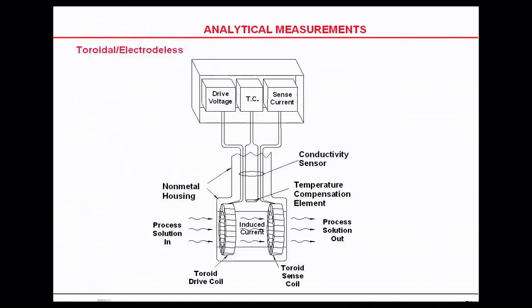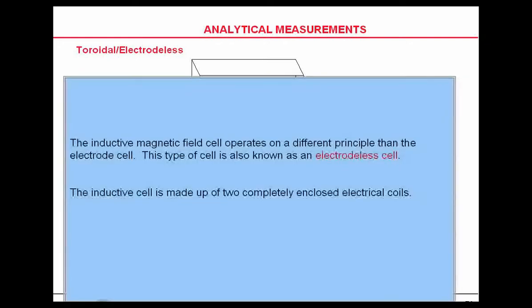Toroidal conductivity is the other way of measuring conductivity. It's generally used for high conductivity or dirty solutions where you can't use the contacting type. You basically have two toroids, one on the left and one on the right. An inductive magnetic field operates on a different principle than the contacting cells.